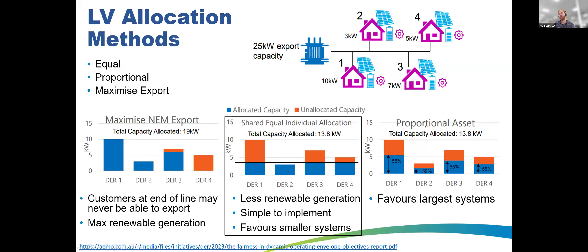Proportional allocation — giving more export to larger systems — is sometimes called more equitable based on system size, but it's essentially pay to play: the more money you spend on a larger system, the more export you get, which penalizes those who can only afford smaller systems. There needs to be more customer engagement work to determine which methodology, or others, is preferred. We're going with equal allocation now because it's technically easiest and reasonably equitable, but a national engagement process is needed, and there may be mechanisms to use maximum export with compensation for end-of-line customers.